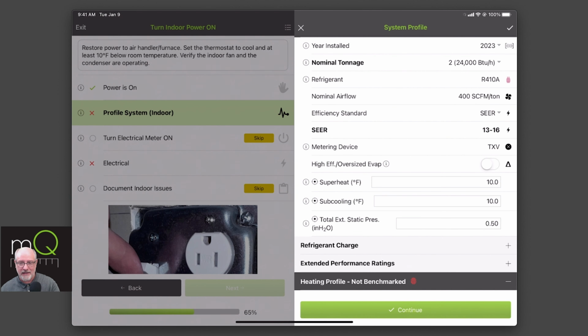If you want us to be accurate, we need to know the defaults here. Your superheat or subcool are based on your manufacturer requirements. Make sure you're looking those up and entering accurate information, because it's plus or minus 3, but it depends on what number you've got here.